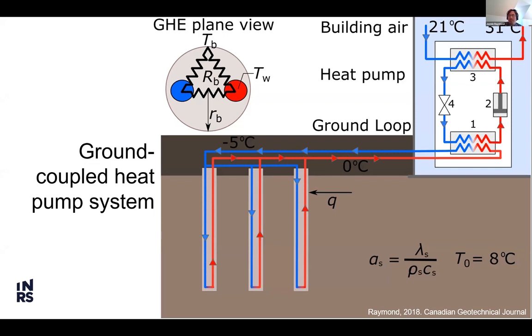air that circulates in your building, and you can heat your building, let's say producing hot air at 31 degrees Celsius to heat the room at 21. So the system needs an input of energy to work. At number 2, it's the compressor, and at number 4, it's the expansion valve to continue the cycle. You need to input some amount of energy.